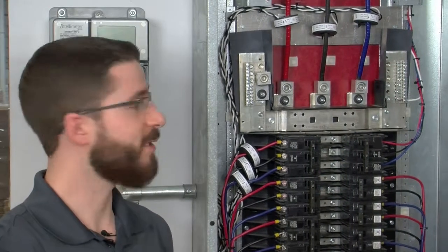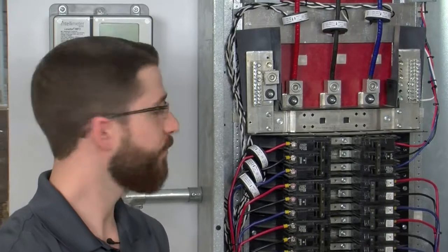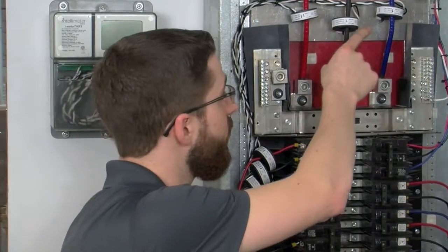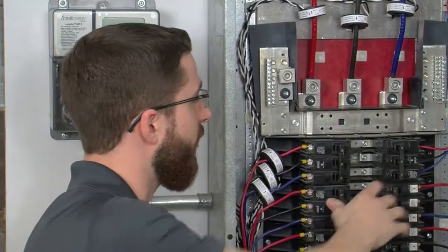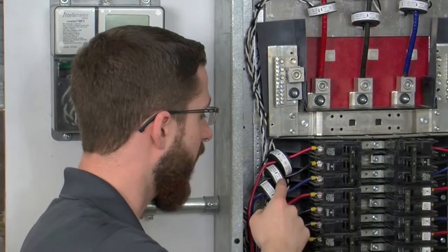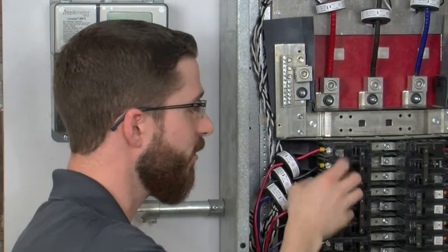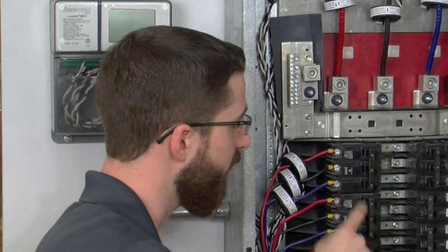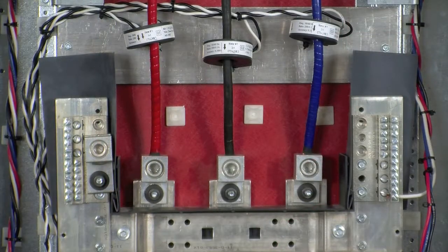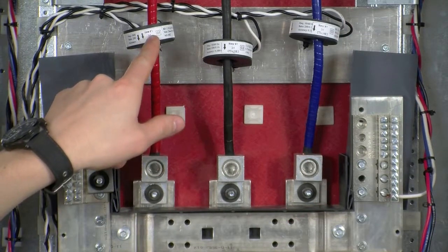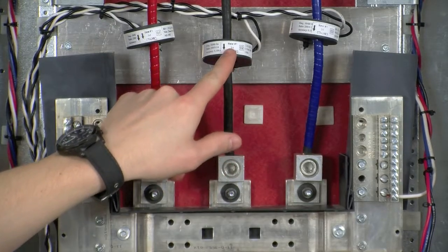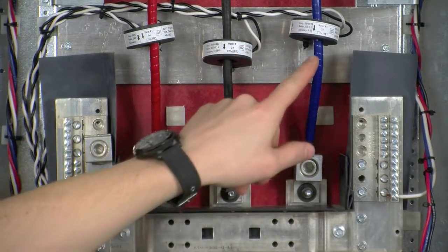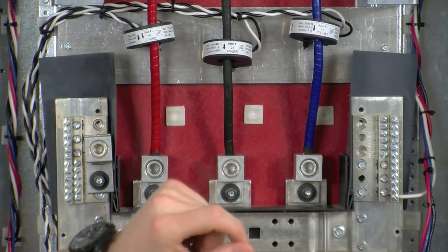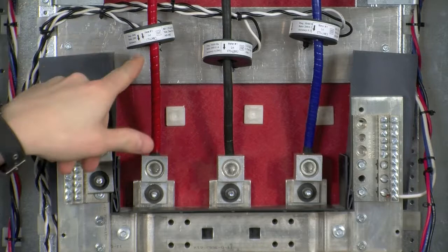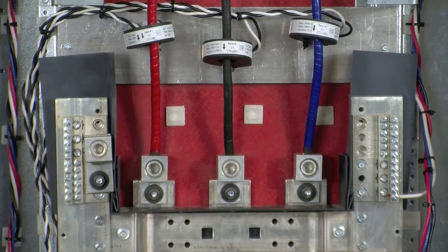Moving on, we're going to first locate the circuit, load, or breaker that needs to be metered. In this case, we're going to use CTs 1, 2, and 3 to meter the main load that feeds the breaker panel. We will then use CTs 4, 5, and 6 to meter a 3-pole breaker located at circuits 1, 3, and 5. So starting at the mains, we're going to place CT1 on phase A or line 1, we're going to place CT2 on phase B or line 2, and we're going to place CT3 on phase C or line 3. Keep in mind that the arrow on the label must point in towards the breakers as current flows in from the top of the panel down into the breakers.